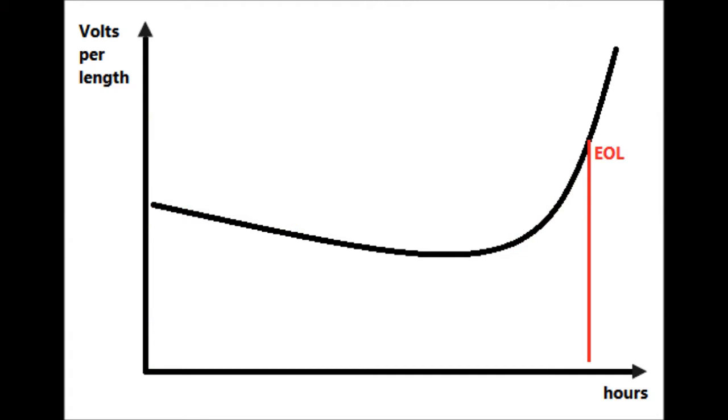I'm showing how the voltage requirement of a neon sign tube looks over lifespan. You see that the tube's life starts off with a bit higher voltage per foot then we have a long period of hopefully many 10,000 hours of lower voltage operation and towards the end of the tube life the curve will turn back up until it gets so high that the transformer can't strike it anymore.